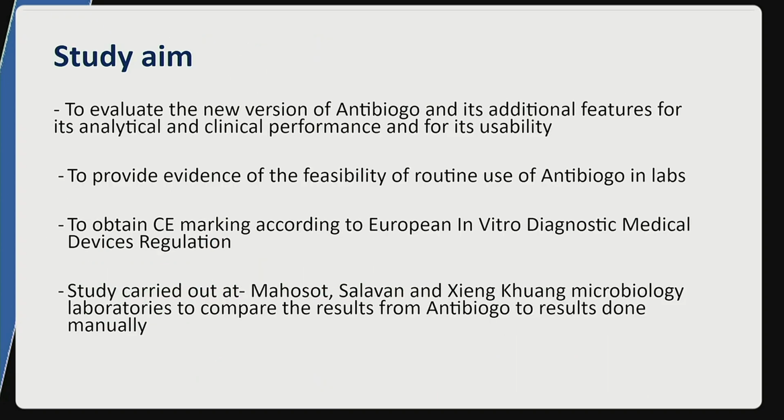Slide. So the aim of the study was to evaluate the new version of Antibiogo and its additional features for its analytical and clinical performance, and to obtain CE marking according to the European in vitro diagnostic medical devices regulations. The study was carried out at Mahosot, Salavan and Xiengkhuang Hospital microbiology departments and compared results from Antibiogo to the normal manual process of AST and the interpretation of the AST zones by microbiologists. Slide.